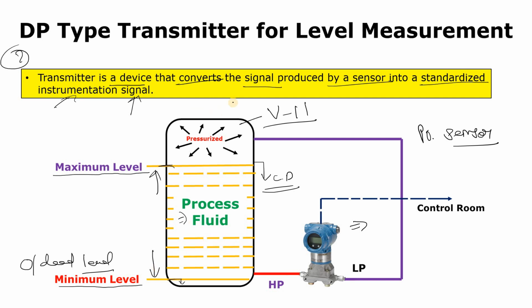Now what I have done is given two tappings: the first is the HP tapping, that is the high pressure tapping, and the other is the LP tapping, the low pressure tapping. The HP tapping is connected at the lower side of the vessel to the transmitter, and the LP tapping is connected to the transmitter on the upper side, and it will always be placed above the maximum level.